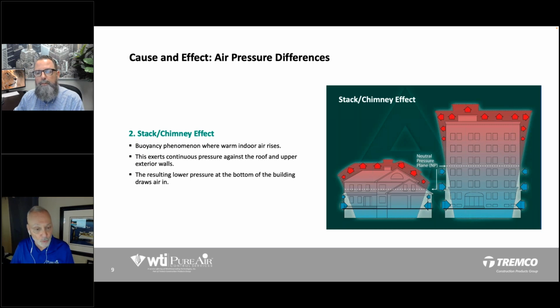And then when we start to cool our buildings, or when we're down south, we have reverse stack pressure. We know cooled air in a building is heavier. It pulls in the warm moist air at the top of the building, and as soon as it starts pulling it in, it starts to form condensation. That's where we see bowing ceiling tiles and stuff like that. And it's a rapid increase of pulling in pollutants from outside, dirt, bugs, insects, all that kind of stuff. So yeah, okay, that makes sense.